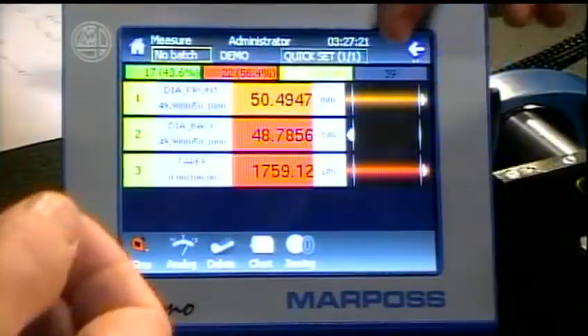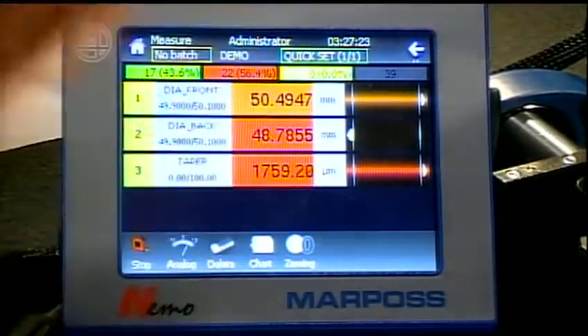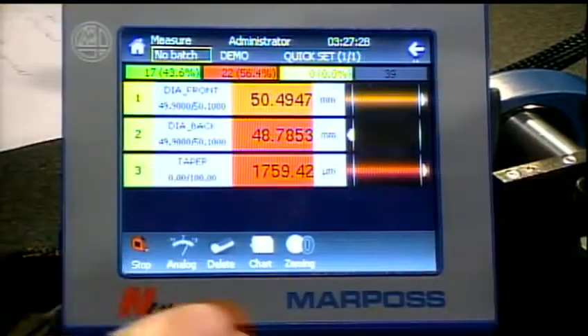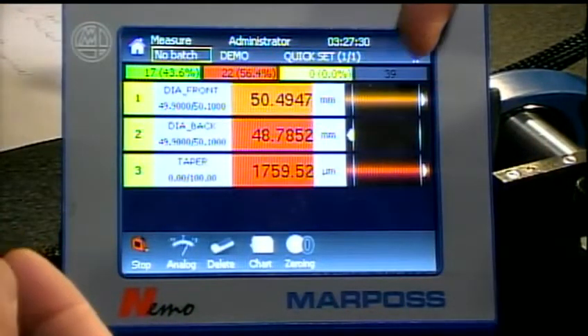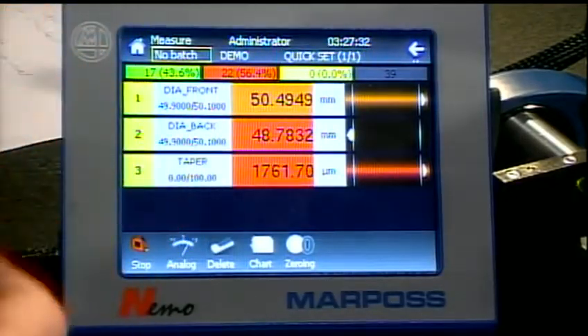So if you want to look, am I approaching a limit, that can be programmed in too, and in this case we look at the Nemo, that shows up as a yellow. So sometimes that's valuable for the operator, rather than just a straight go, no-go, you've passed, you failed. It's nice to know sometimes when you're approaching a limit, and so we have that approach light built in there.